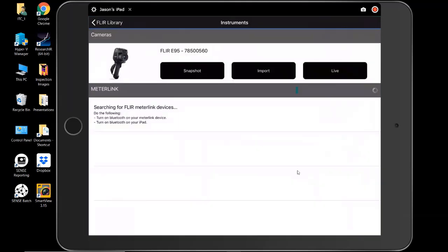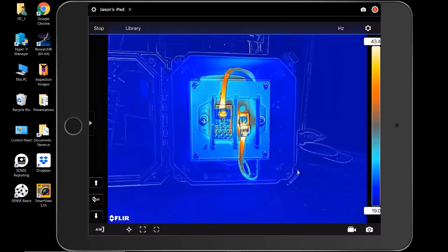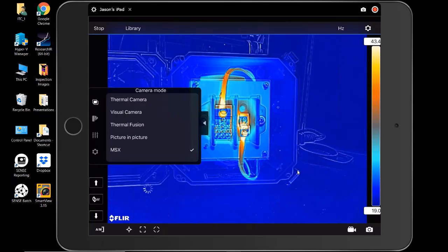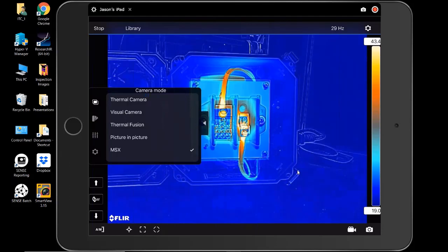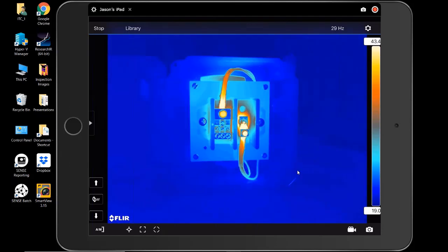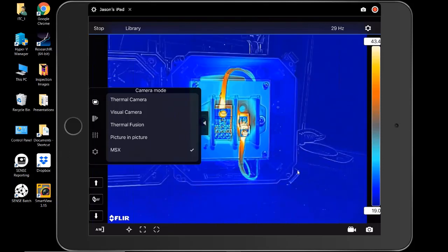Most new infrared cameras have two feeds, two detectors in them. One is the thermal detector, the other is the visible light detector. That takes your control photo, your digital photo, like from a digital camera, which you can use in an infrared report. And that feature in the software blends those two together to give you better contrast, better detail of the situation. A little bit different from MSX, where MSX takes the elements of contrast, like the edges of objects and detail, and pulls those things out and lays that over on the image as well. Hopefully I think the delay is gone, right?